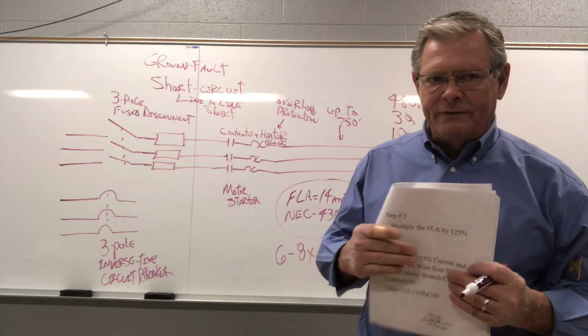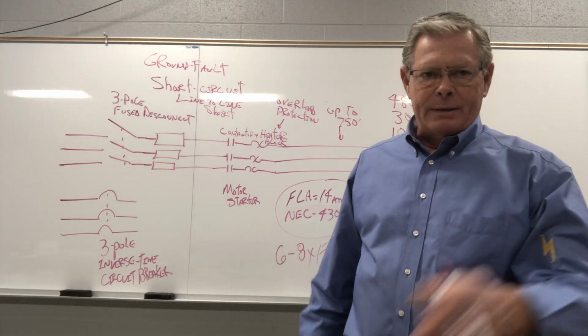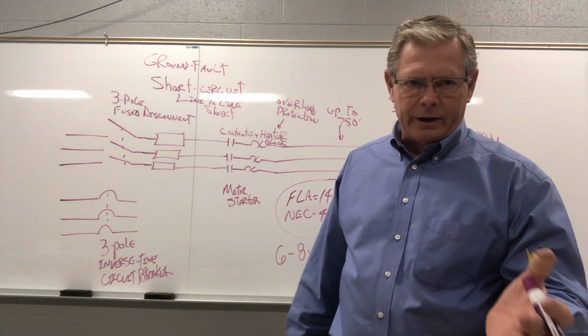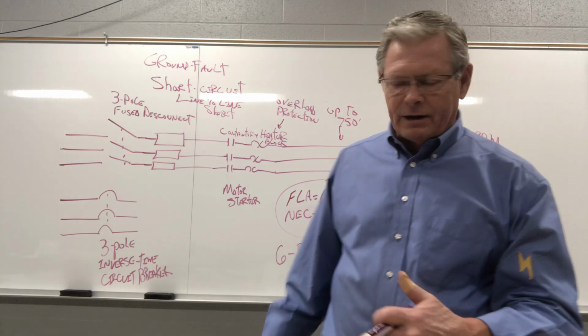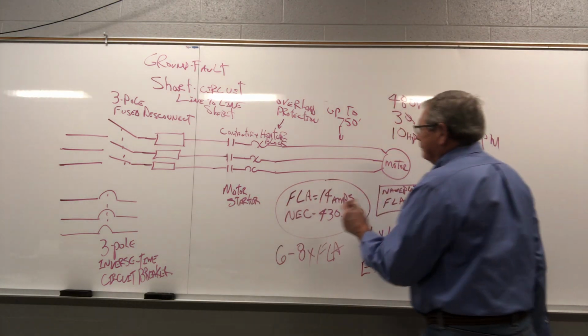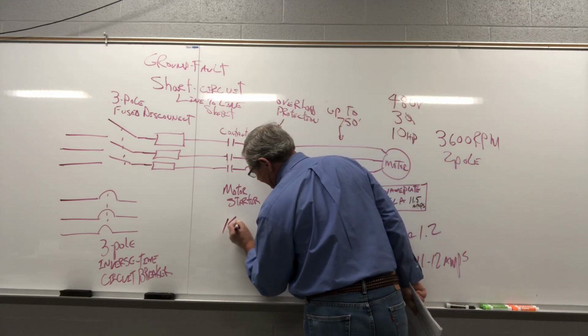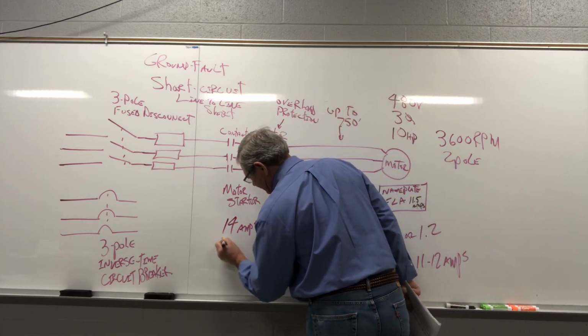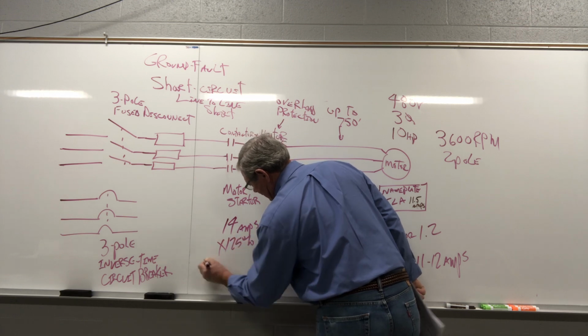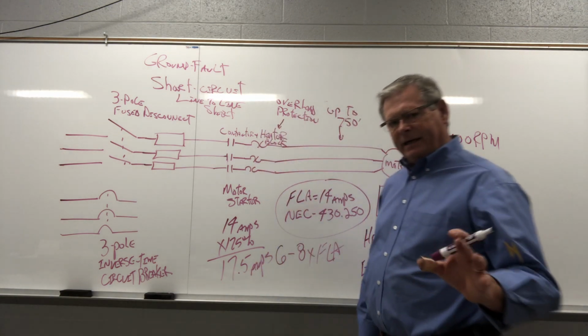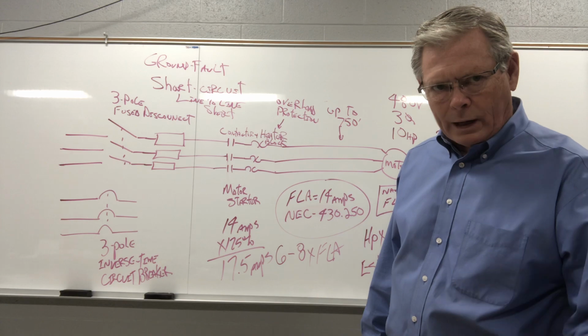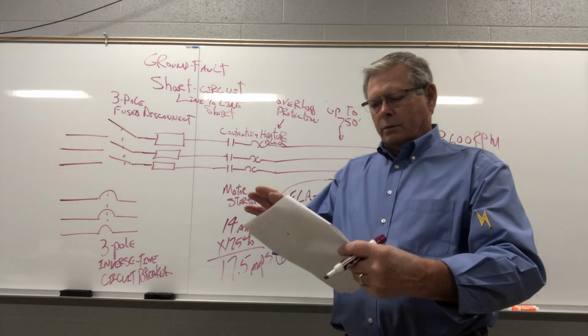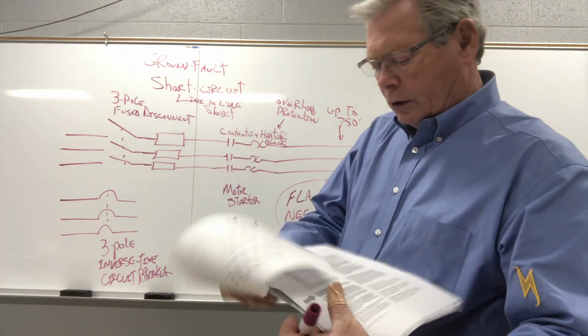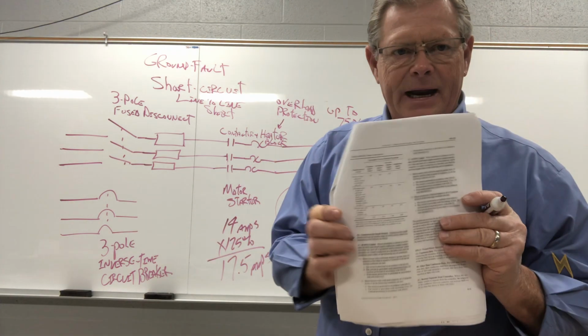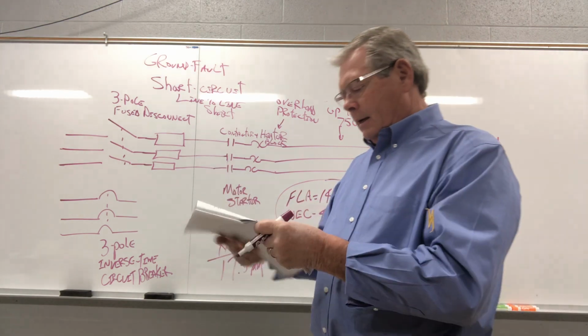So we have to add a 25% factor to keep that wire from degrading the insulation from starting current. Because that insulation has to last forever, right? So 14 amps times 125% equals 17.5 amps. Now 17.5 amps is what we're going to use to select wire. So we're on the step 2 page. Let's go to the next page over. And you're going to see an arrow right here. I'll tell you what that arrow says.